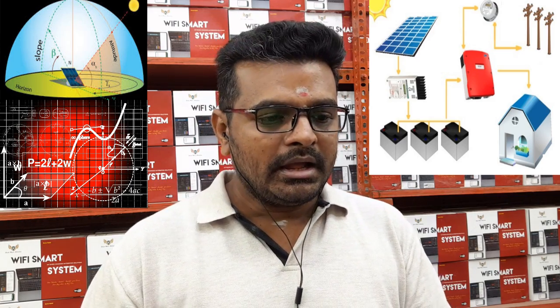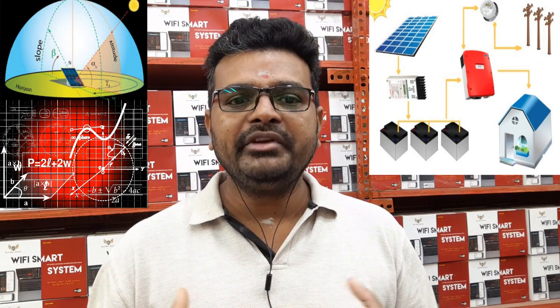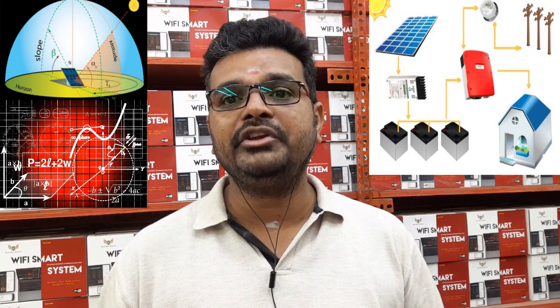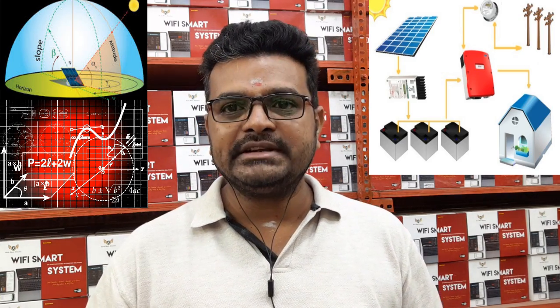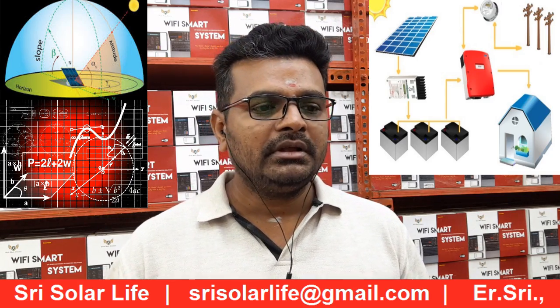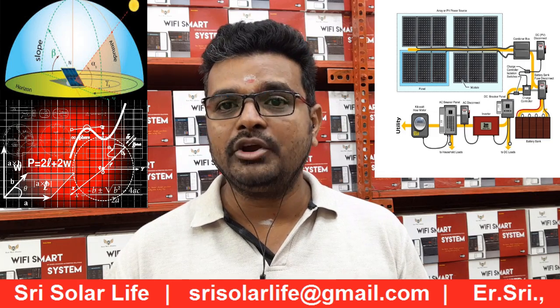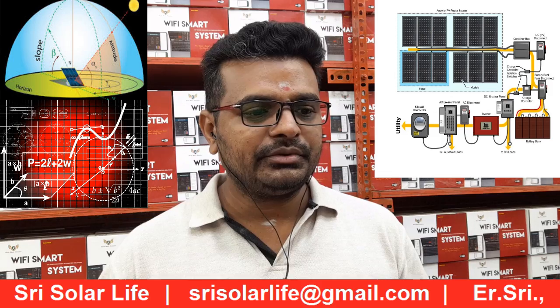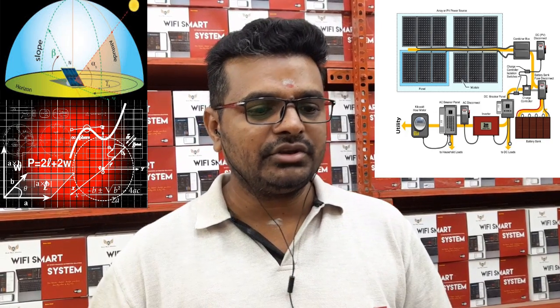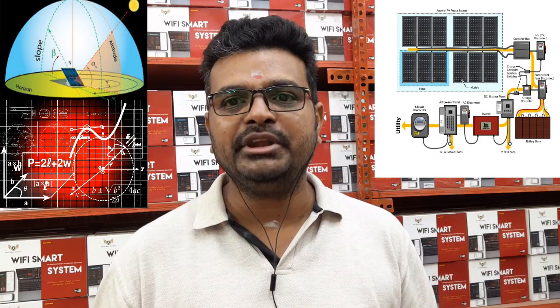We have considered polycrystalline panels here. We take historic weather data for this location — we don't just consider a single year; we take historic data and calculate all weather conditions exactly for this location. We also factor in the panel specifications when sizing. It's not just a plug-and-play job. According to these calculations for this location, you need to go with a 4600 watt polycrystalline panel system to achieve the required units — meaning to generate that many units for that location.